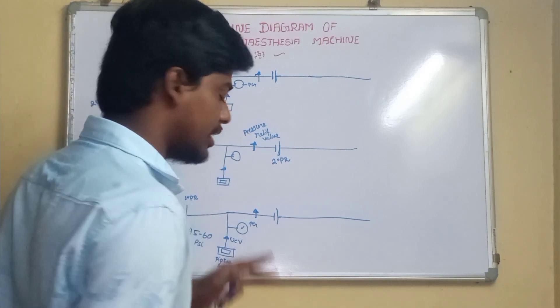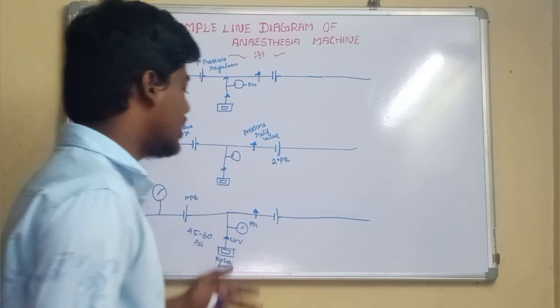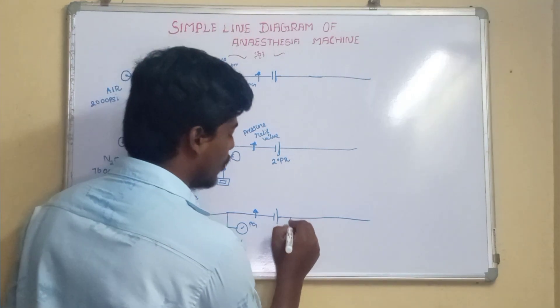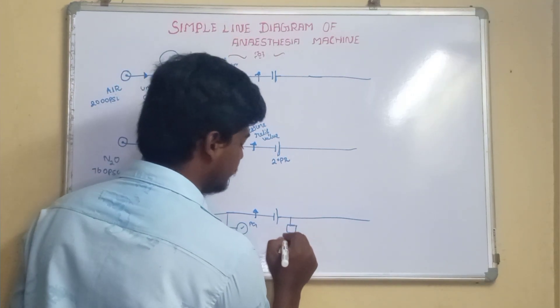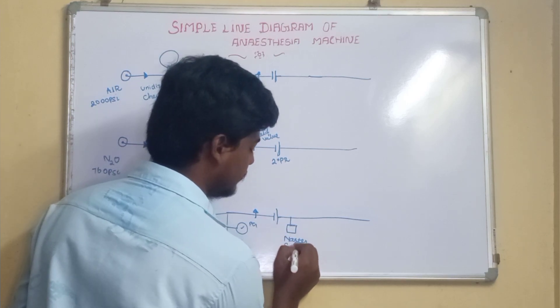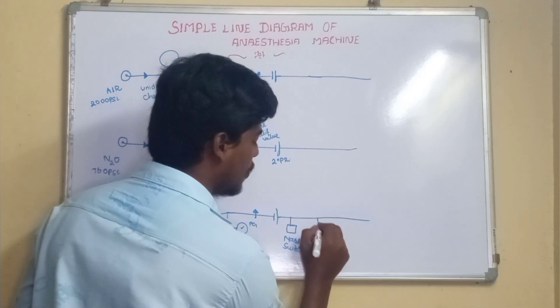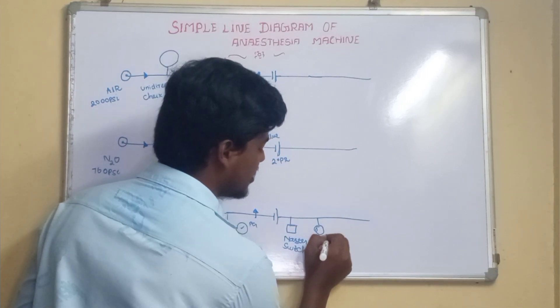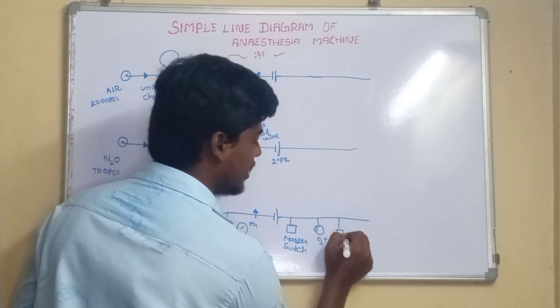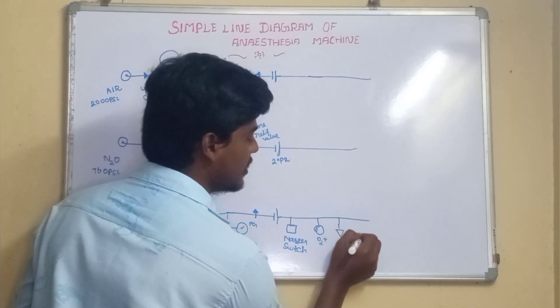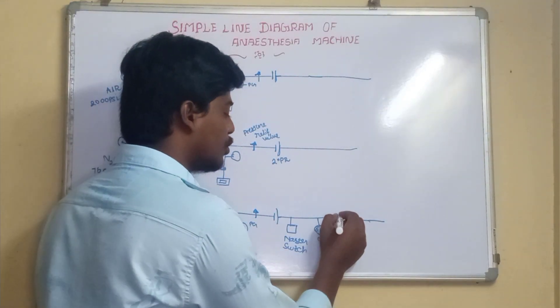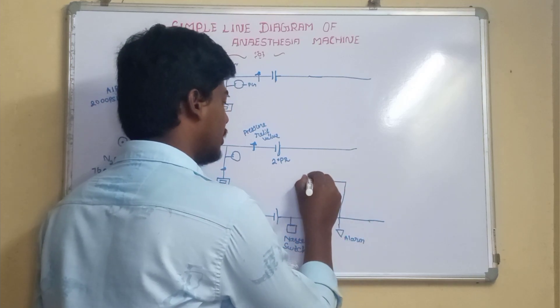After the second-stage pressure regulator, the oxygen line has some specific special connections. One is the master switch, another is the oxygen flush, and another is the oxygen failure safety alarm. This oxygen failure safety alarm is also connected with the other two gases — air and nitrous oxide.